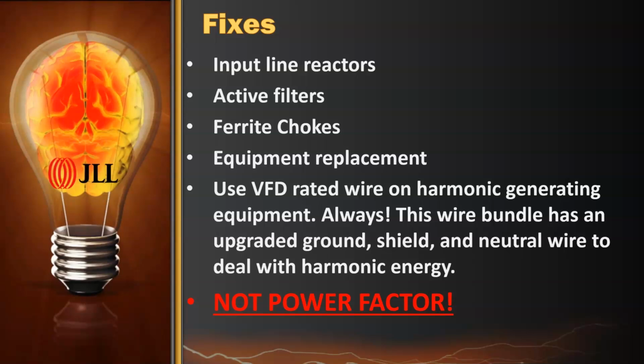Here's another one. Would it make sense to install a ferrite choke preemptively on equipment that typically causes harmonics, like chillers, pumps, etc., or will the chokes cause issues if there's no harmonics present? Yeah, that's a great question. And in addition, if you're an ESCO doing this for clients, that's probably a smart thing to do if they're going to be measuring the utility bills and looking at savings that way. From an ESCO point of view, I would do it, especially if I knew the equipment was a chiller. I would do it for sure.